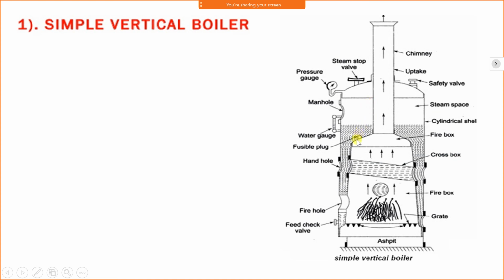Then a fusible plug is provided here. Suppose the safety valves are not working, or the water level inside the boiler is very low and the temperature of the boiler is increased beyond its capacity, then the fusible plug will melt, and it will create an opening for water to enter the furnace, and the combustion will be extinguished.